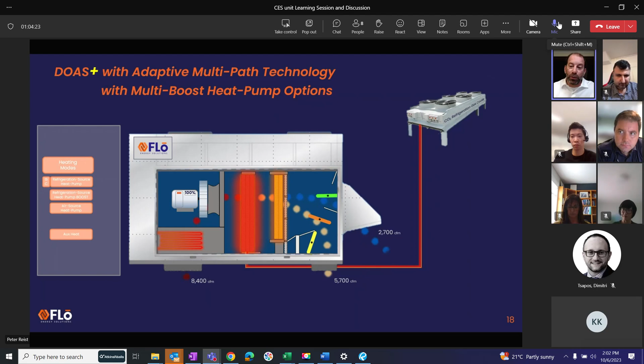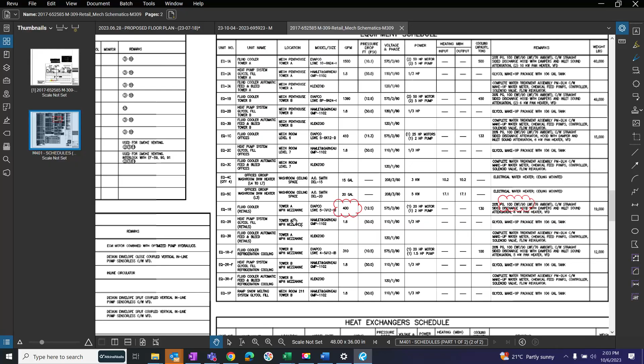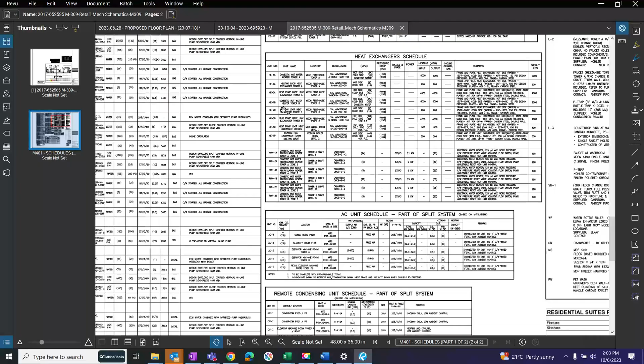The other reason for auxiliary is insurance companies like it, because it's kind of the safe thing that's there. If your refrigeration rack is down, we don't get any reclaim. If your water loop is down, we don't get any water source heat pump. So insurance companies often still require that last stage coil at the end. So I'm assuming you're planning something of that sort - do you know any more details, electric or...?